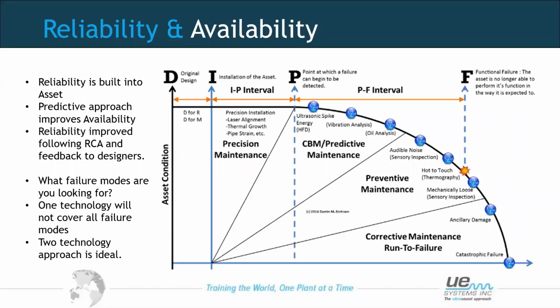Now, we can also use that as a predictive, but also as a proactive approach when we think about lubrication. Again, with lubrication, we're talking about friction. So if we're using the ultrasound device with an asset that is in good health and requires lubrication, we can use the ultrasound to monitor the friction as the grease is applied to the asset.